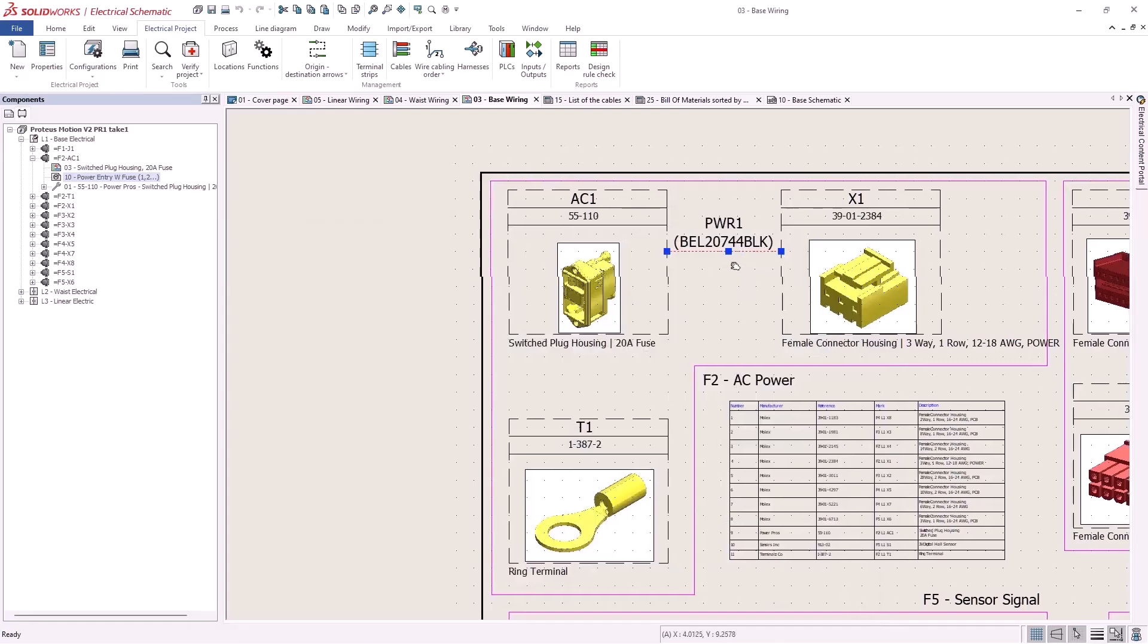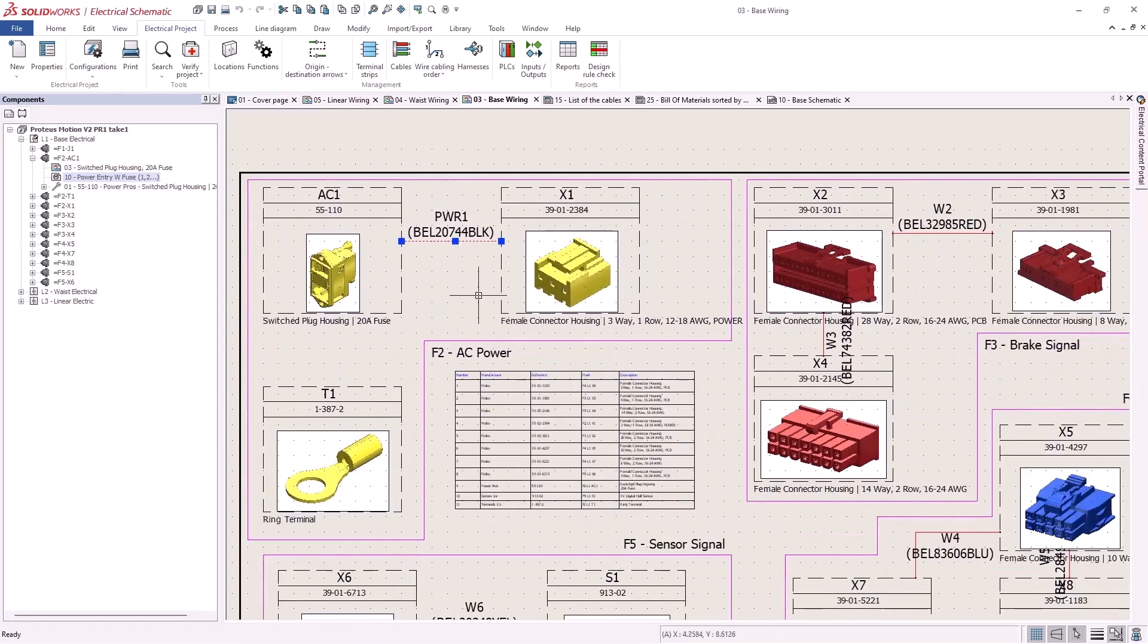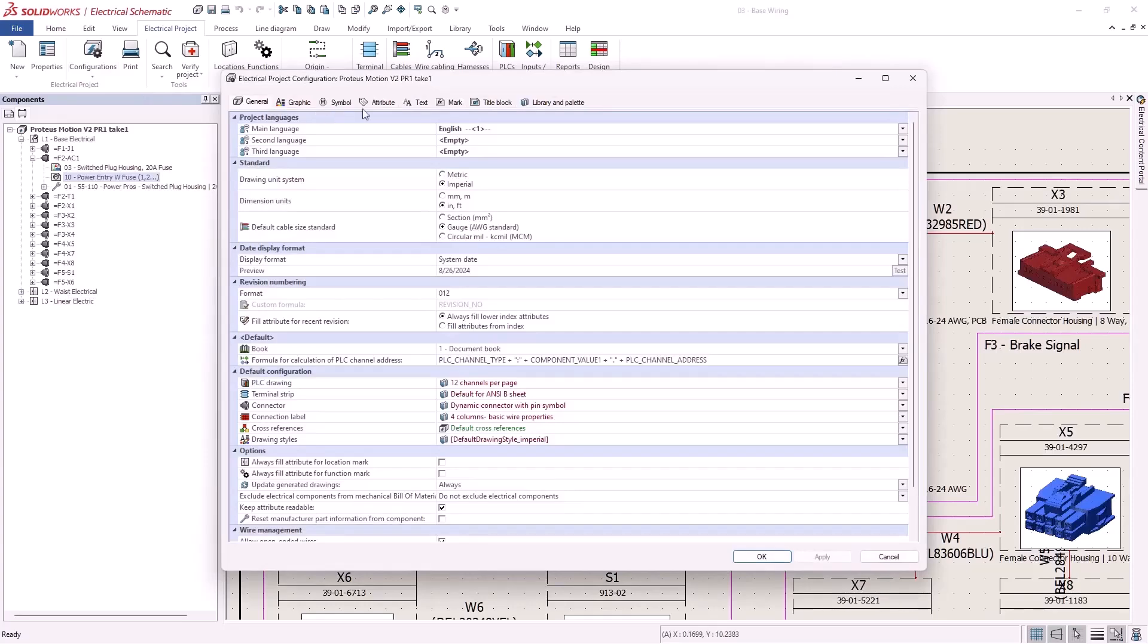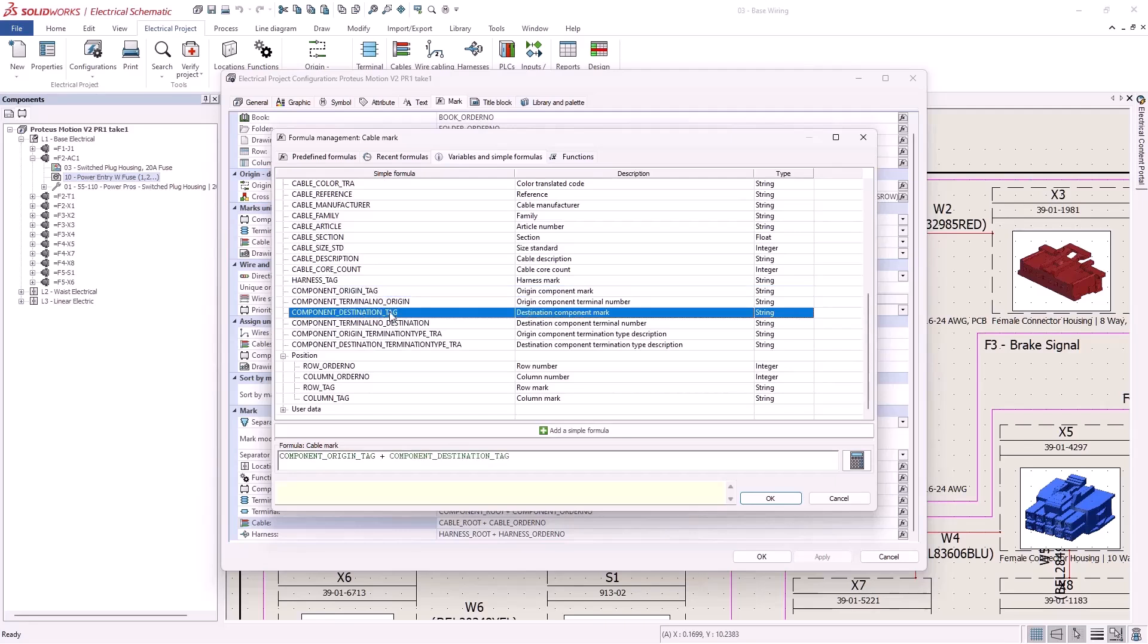If I want to get more sophisticated in my naming I can use new variables that have been added to cable mark formulas like position variables, origin and destination variables. If we modify the cable mark formula to the origin and destination component, this can help save you time by making it easier to identify which component a particular cable is attached to.